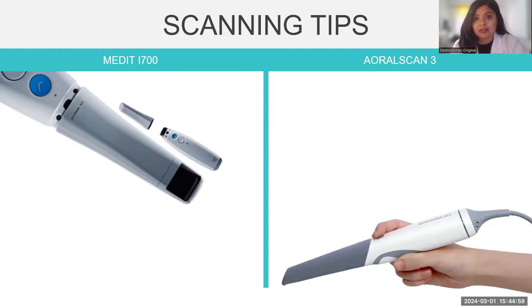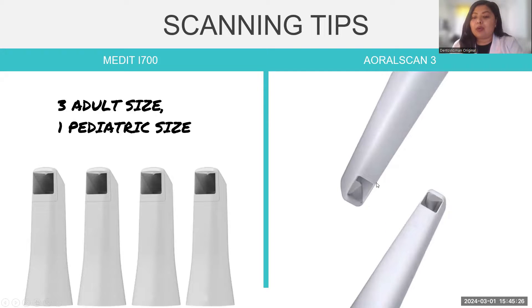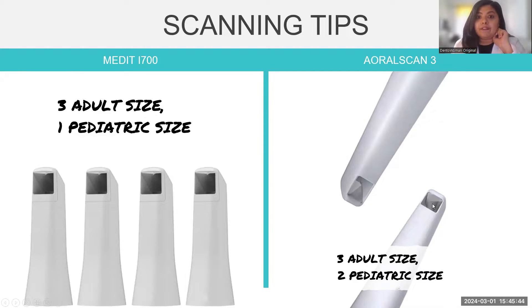For scanning tips, the Medit i700 has a 180-degree reversible tip — it can be fitted either way — whereas the Aoralscan 3 tip has a particular direction in which it must be fitted. I personally didn't find this a big difference while scanning; you develop your own method. For additional tips, Medit i700 comes with four extras including one smaller pediatric tip, while Aoralscan 3 includes five extras — three for adults and two for pediatric patients. The smaller tips are very useful for restricted mouth opening cases, female patients with limited opening, or scanning second and third molars.